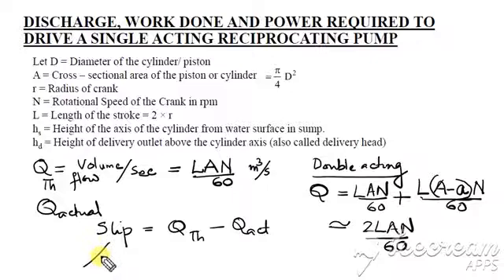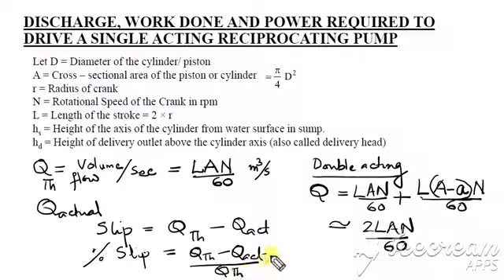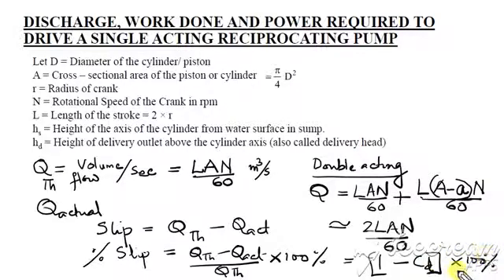Usually, we express slip as a percentage. Percentage slip equals (Q-theoretical - Q-actual)/Q-theoretical × 100. This is also written as Q-actual/Q-theoretical, which is Cd, the coefficient of discharge. You can write this as (1 - Q-actual/Q-theoretical) × 100, which equals (1 - Cd) × 100.